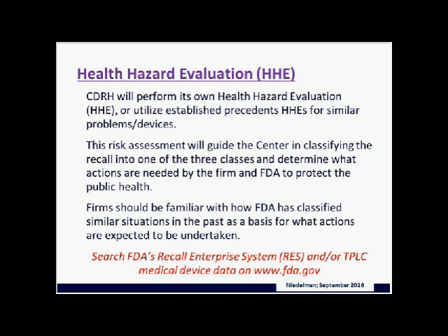Defining a risk, there are a number of factors associated with that. The technical assessment of the defect defines the likelihood of the device failure, and the clinical understanding helps clarify the risk associated with the use of that device failure. FDA assumes, when they evaluate their HHE and evaluate your product, that no corrective action has been taken by the firm. They don't want to evaluate a situation where the firm has remediated the issue or put mitigations in place. They want to evaluate the problem that existed and prompted your action.